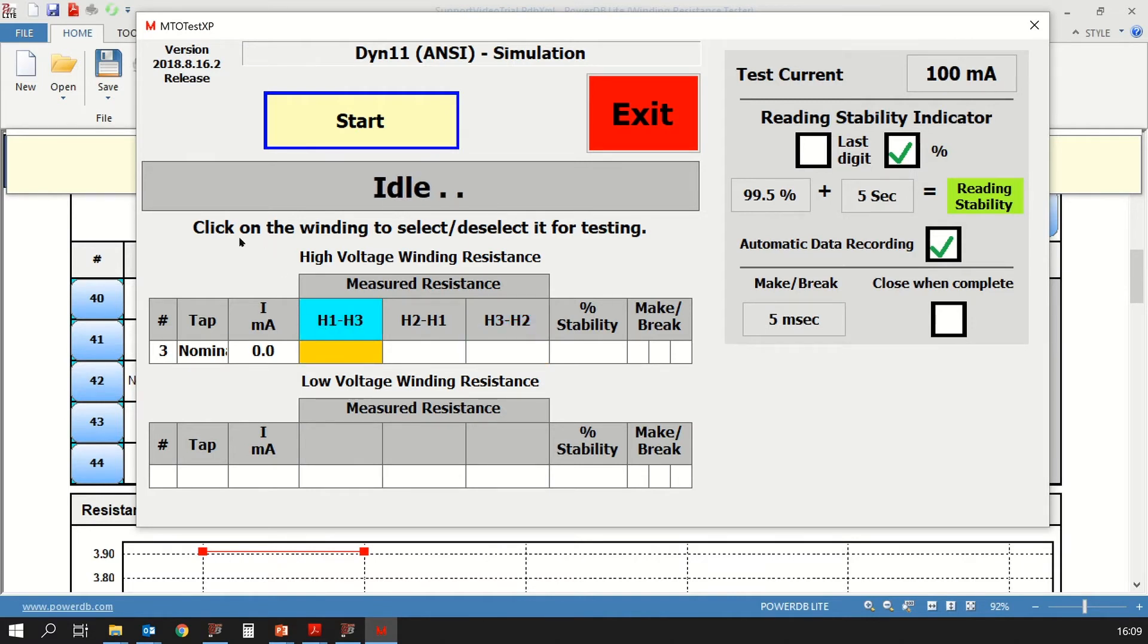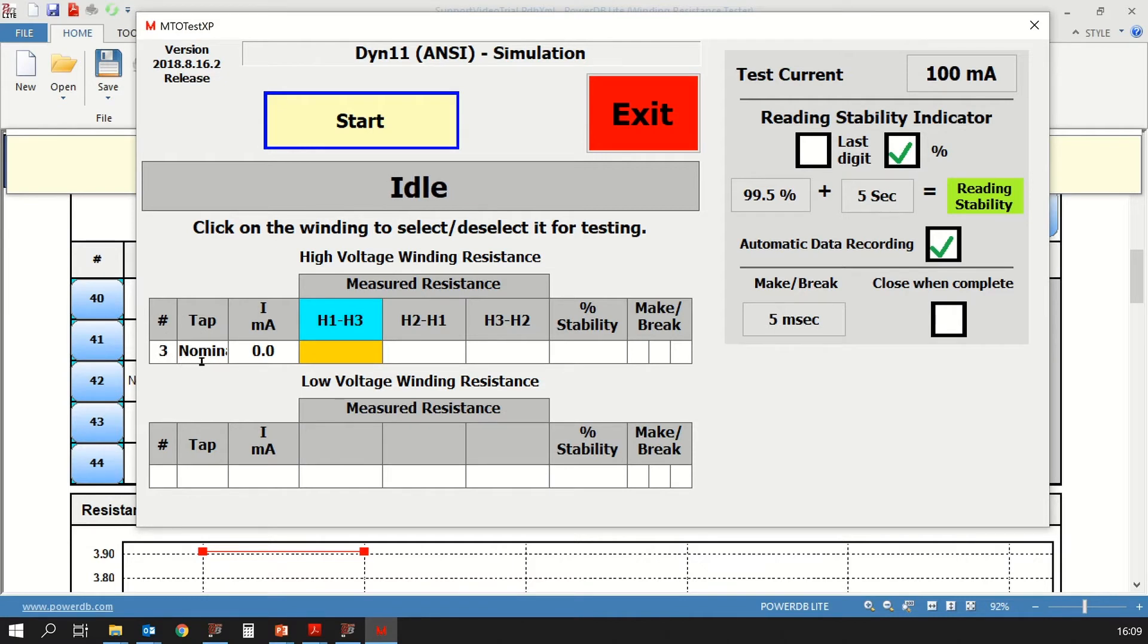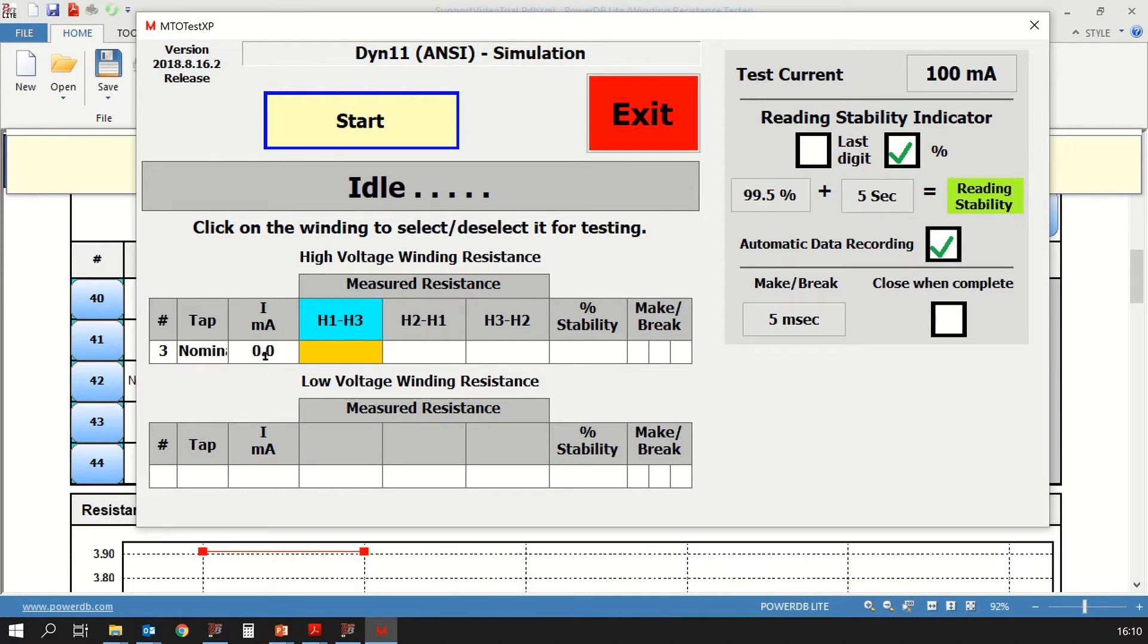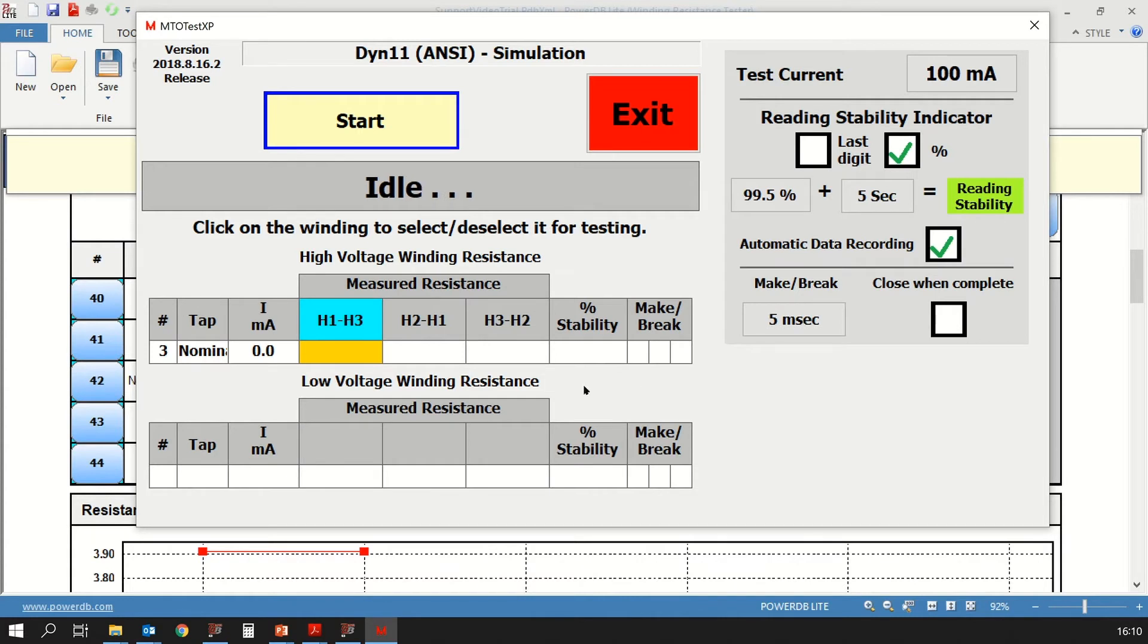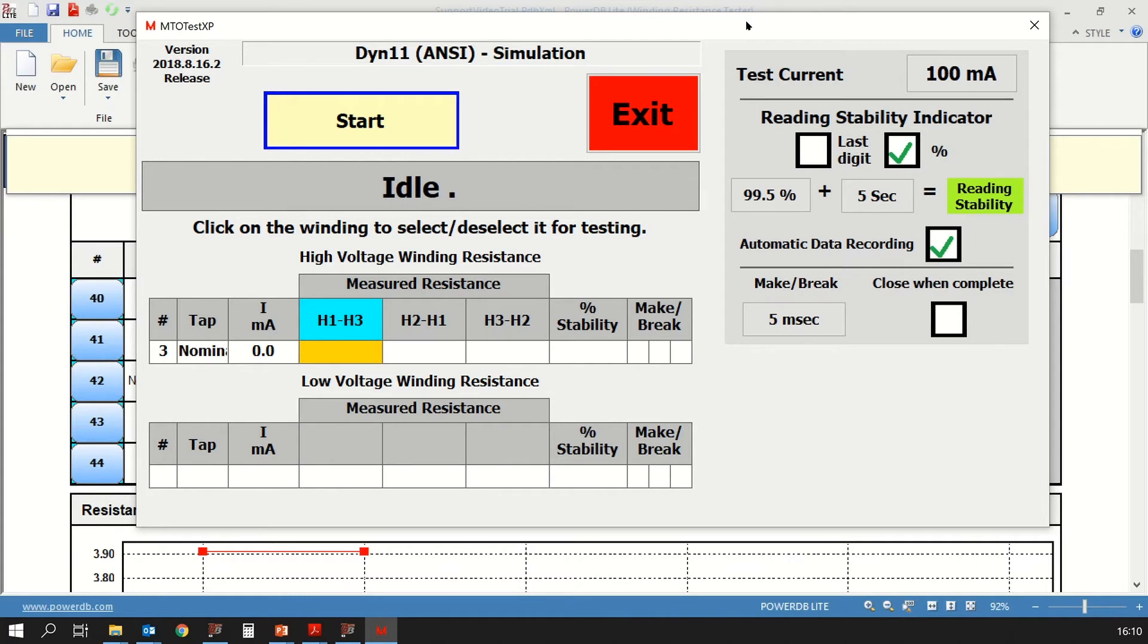In addition to that, you have the nominal tap or tap number three that's selected, and you have the current here that's 0 right now, but that will be the test current that will be applied. Then to the right side of the table, you have the stability indicator. If you're testing on load tap changers, you will have the make before break sensitivity. The same applies even to the low voltage winding.